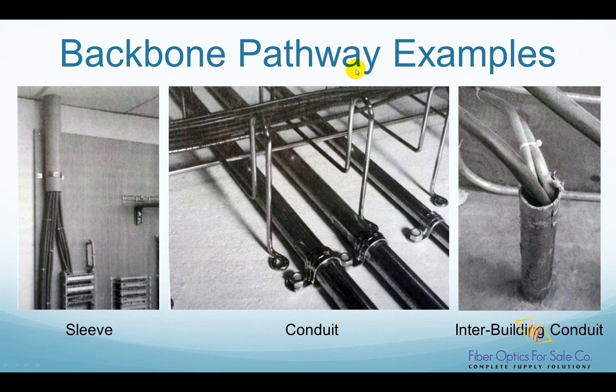Backbone pathways are the cabling facilities designed to hold, protect, support, and provide access to the backbone cables installed between telecom rooms. Designing and installing the backbone pathway is extremely important because the pathway will always exist even if the backbone cables are changed. A well-designed and installed backbone pathway will enable backbone cables to be changed easily and with the least amount of disruption to the communication system and cost. Several different types of pathways are shown here.